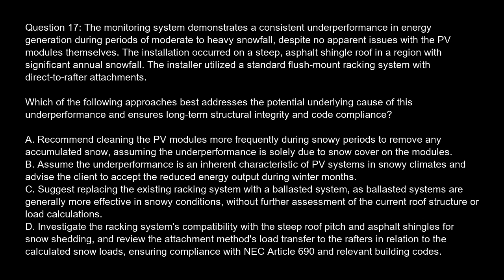Option C: Suggest replacing the existing racking system with a ballasted system, as ballasted systems are generally more effective in snowy conditions, without further assessment of the current roof structure or load calculations. Option D: Investigate the racking system's compatibility with the steep roof pitch and asphalt shingles for snow shedding, and review the attachment method's load transfer to the rafters in relation to the calculated snow loads, ensuring compliance with NEC Article 690 and relevant building codes.